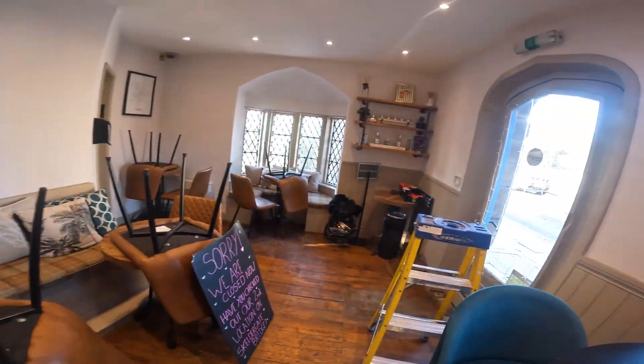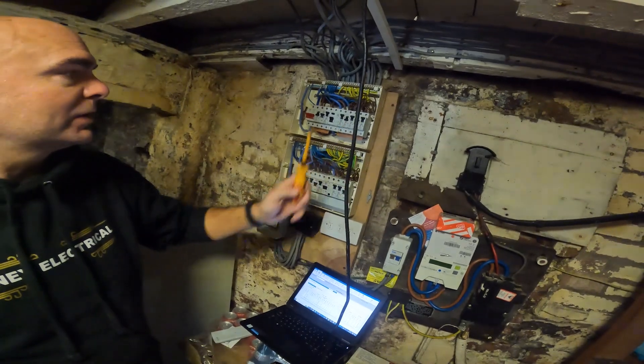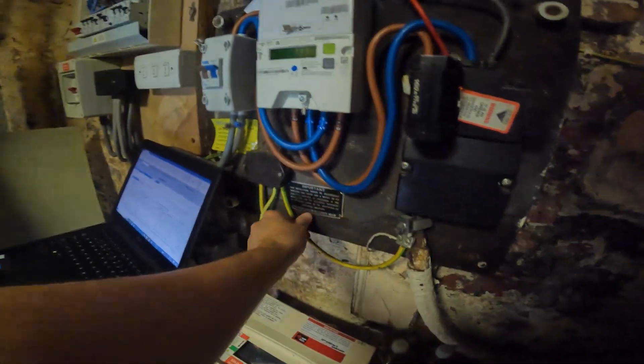This is what we're testing. Brian's downstairs cracking on. Nice little curly-whirly into a little top room - it's tight. We're going to do socket sizing out. Sent Jonah up to plug in. I'll run around and do a visual - make sure there's no cracked switches, cracked sockets. We're looking for verification of connections and singles exposed that shouldn't be. We'll have to check if that's double insulated or not, and the correct cable size for the correct breaker size.